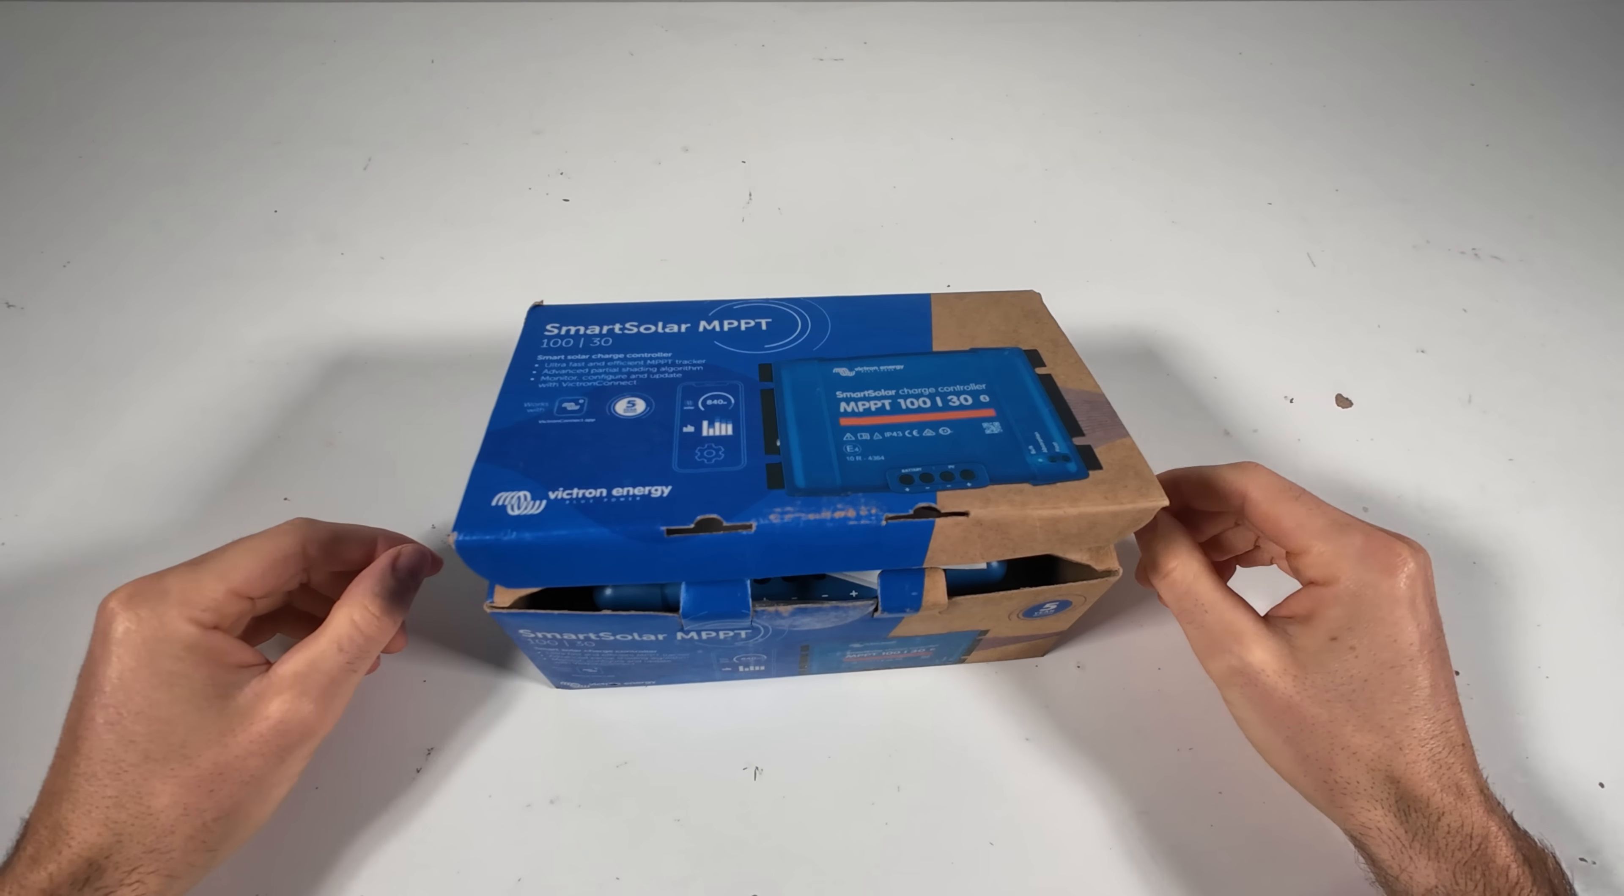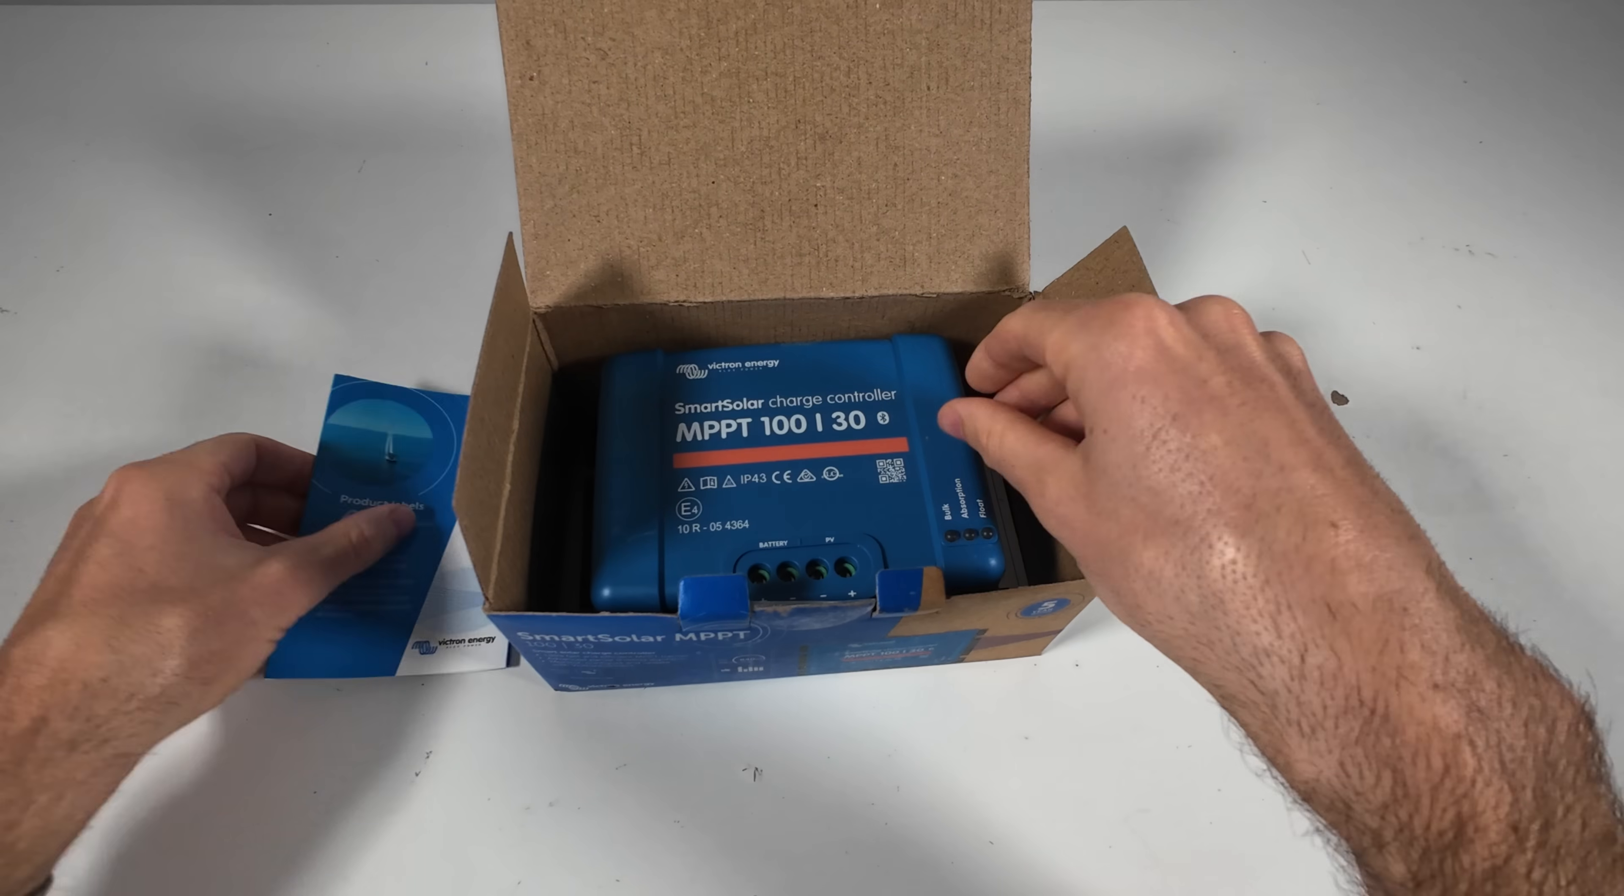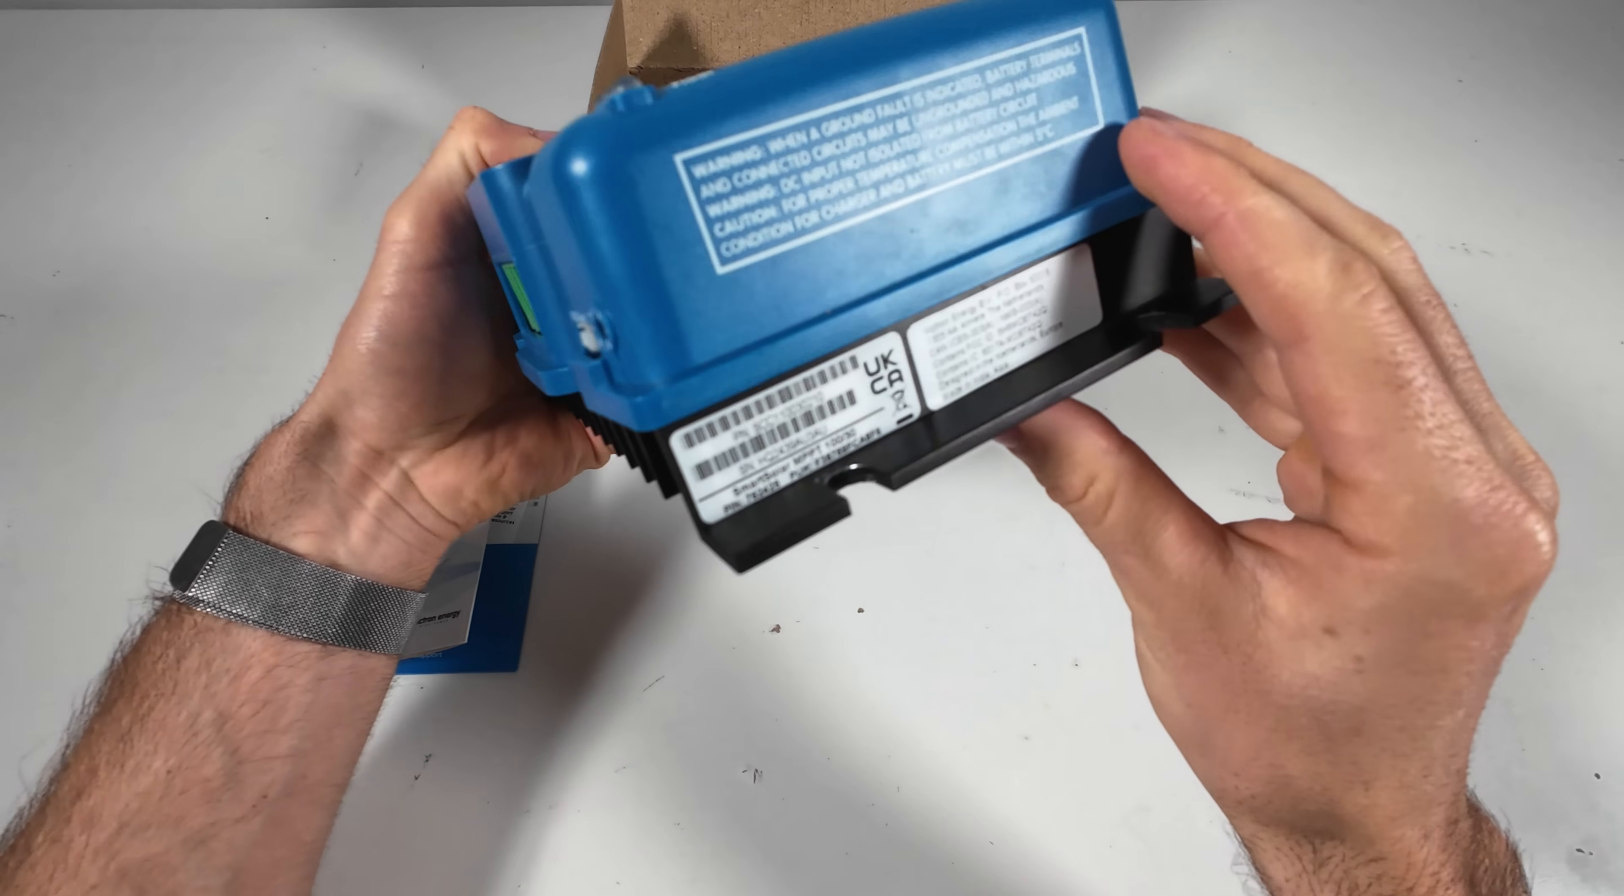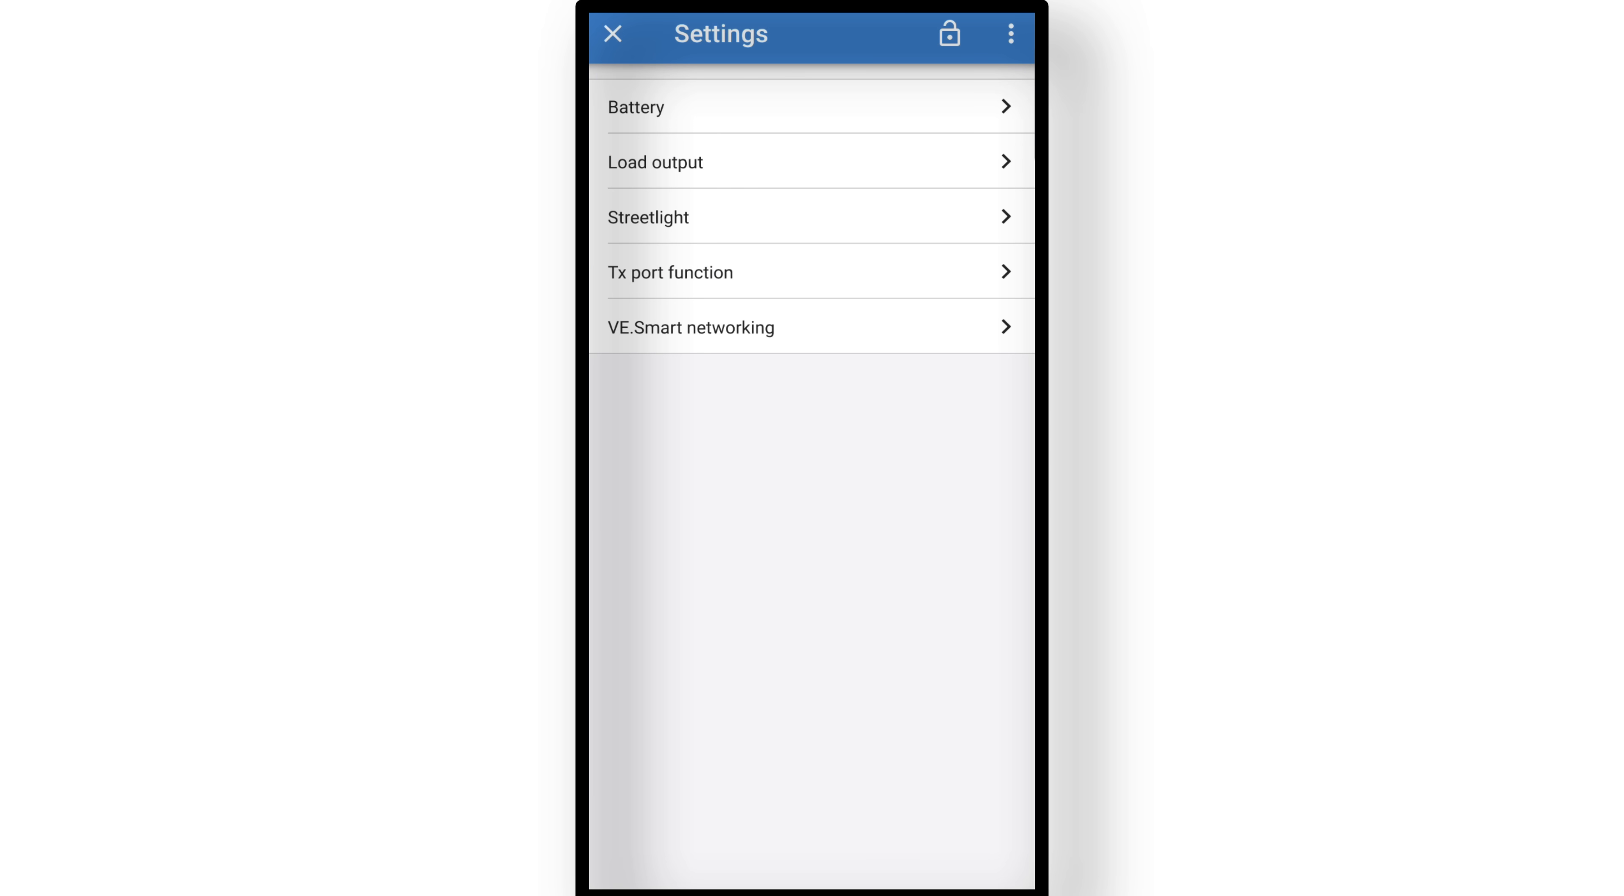Let's take a look at the Victron Connect app. You can download it for free on both Android and iPhone. When you first connect, the app will ask you for a pin code. You will find that code on a sticker on the side of the controller, or sometimes it will be inside the box. And once it's paired, the MPPT shows up in your device list. The very first thing I recommend is running a firmware update. After that, go into the settings by tapping the little gear icon.